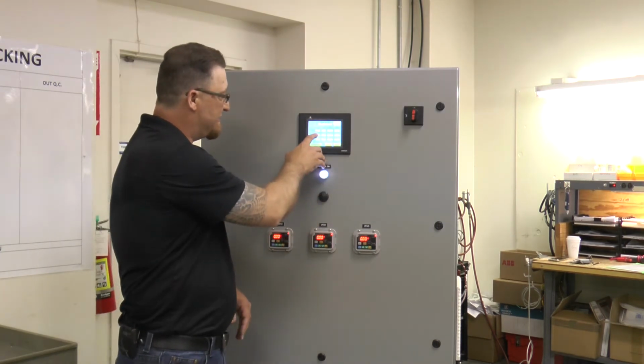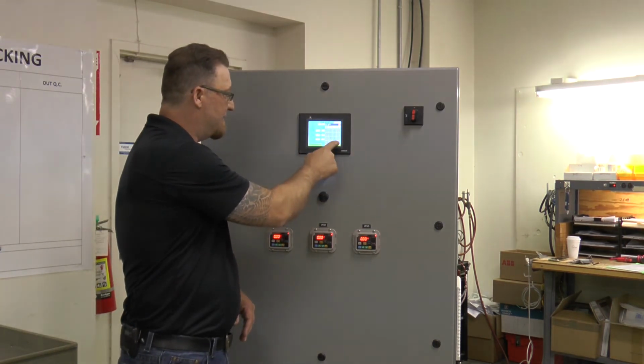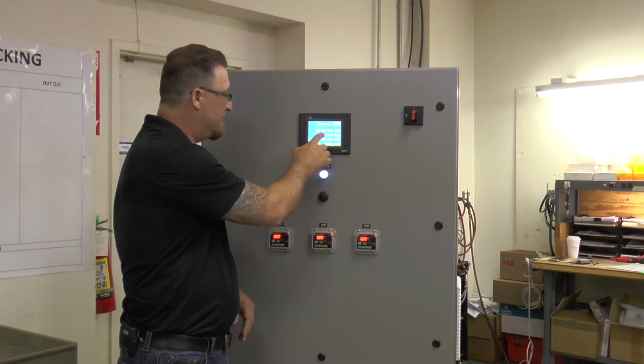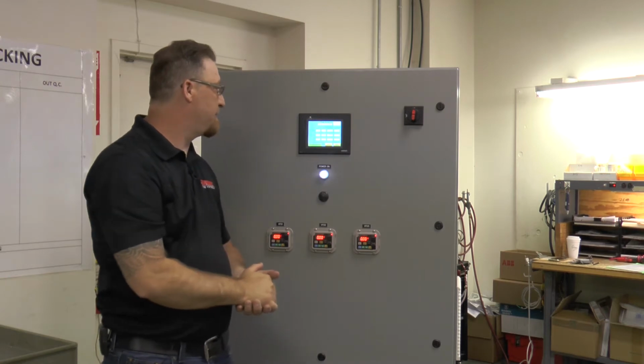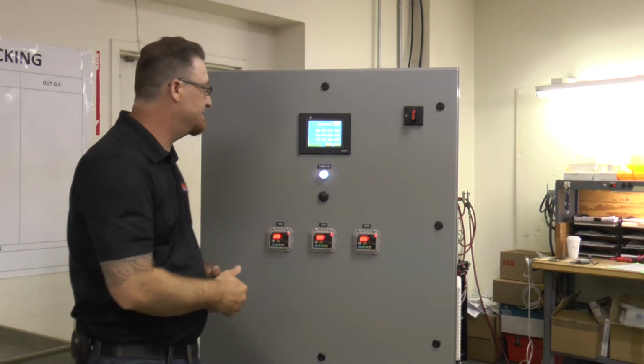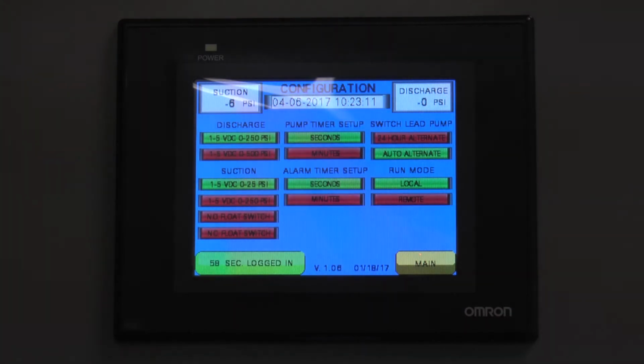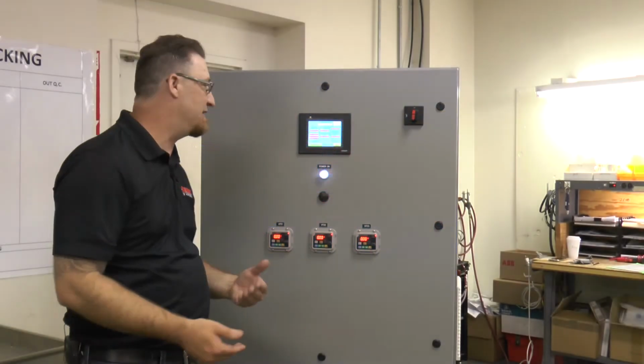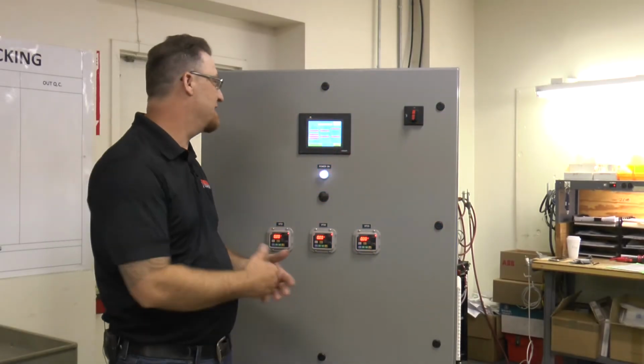And then I can go through this with our lag. I can drop the pressure down a little bit lower than the lead stop pressure, and set on and off delays. You can do that through each one. So when we go to the configuration screen, here is where you set up your discharge pressures, your suction pressures, whether you have float switches, if you want your timers to be in seconds or minutes, and alarm times. How fast do you want those alarms to trigger once it sees that alarm? Do you want it in seconds or do you want it in minutes?